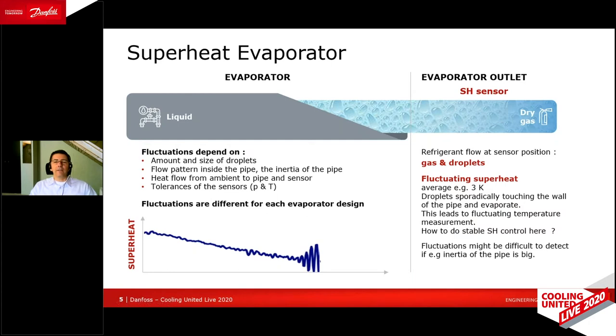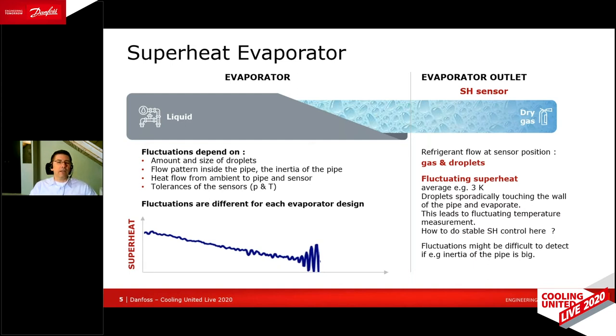That gives instabilities in the superheat measurement — it goes up and down whenever a droplet hits and evaporates. That's the point where we should stop reducing the superheat, because now we have stable droplets leaving the evaporator. We should increase a little bit again to come back to a stable superheat.